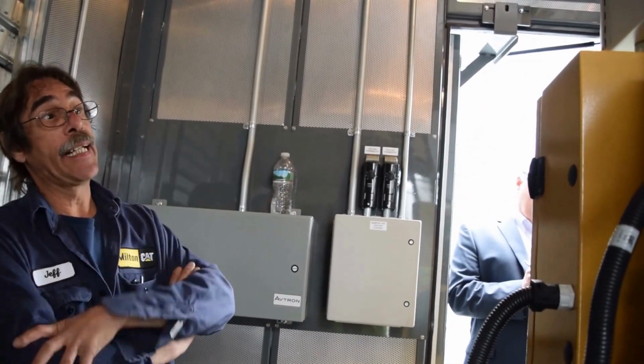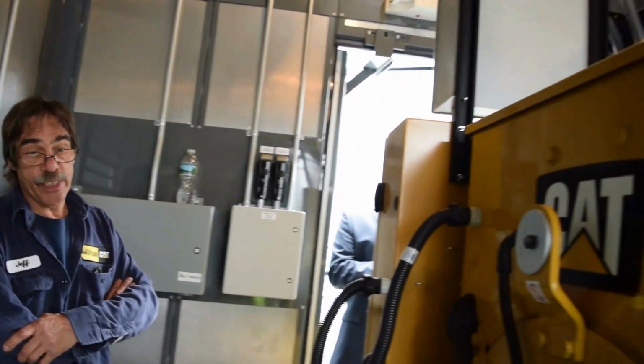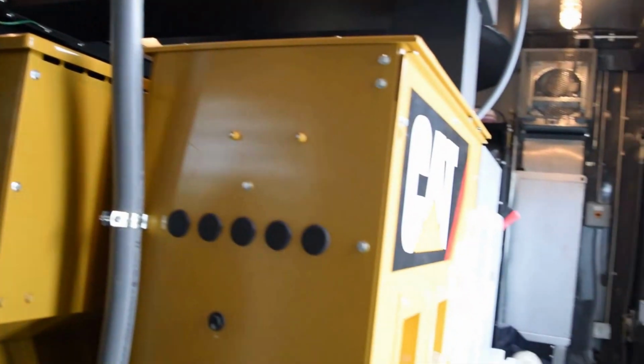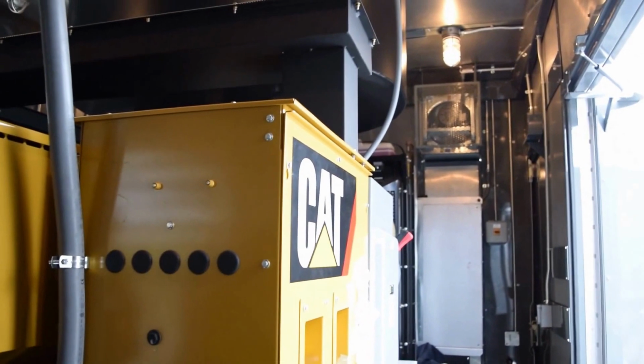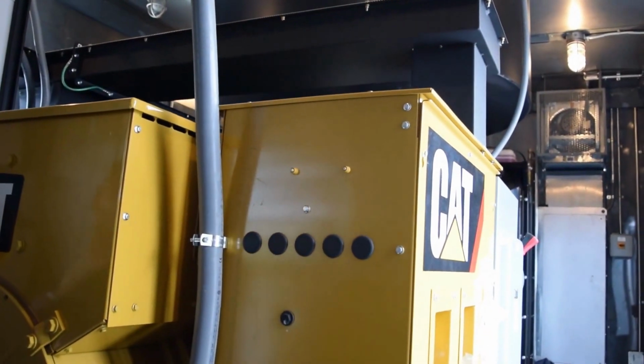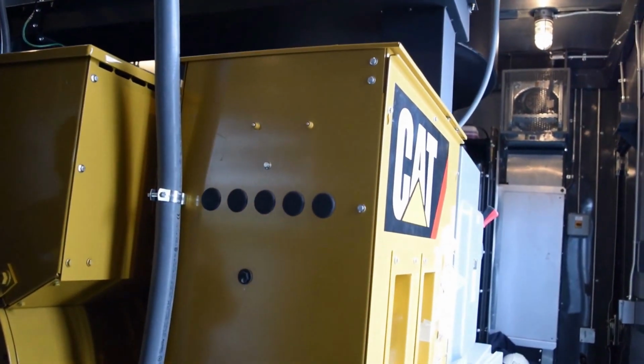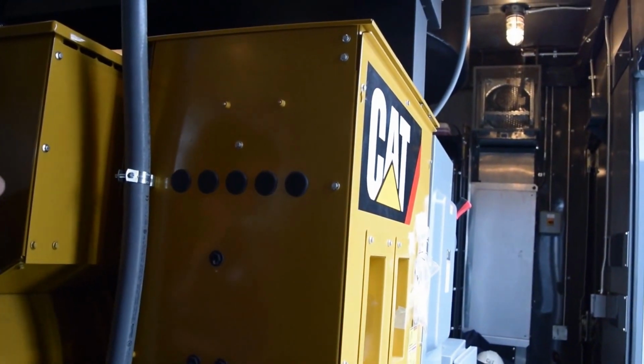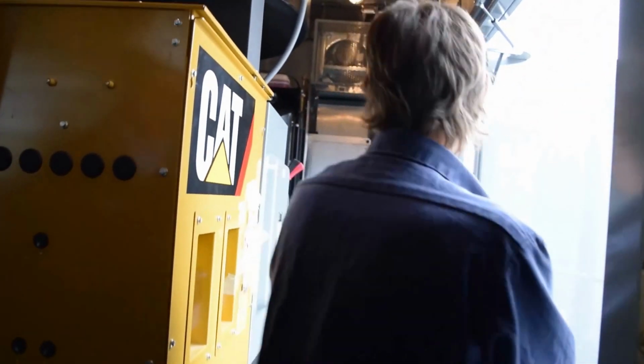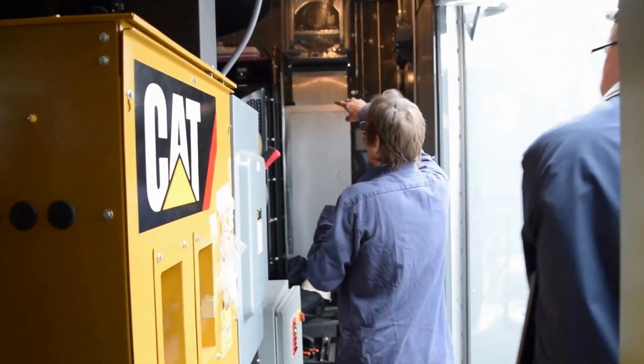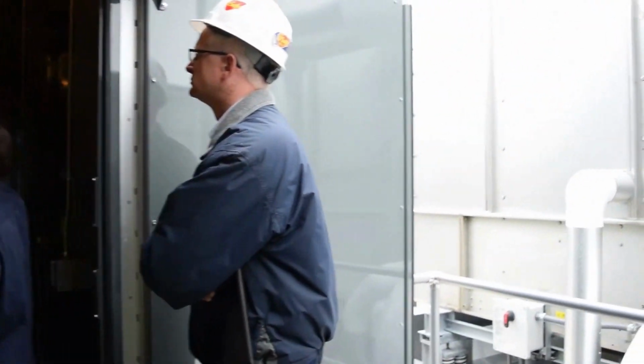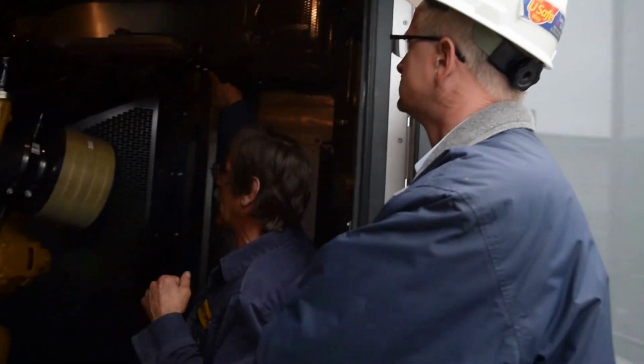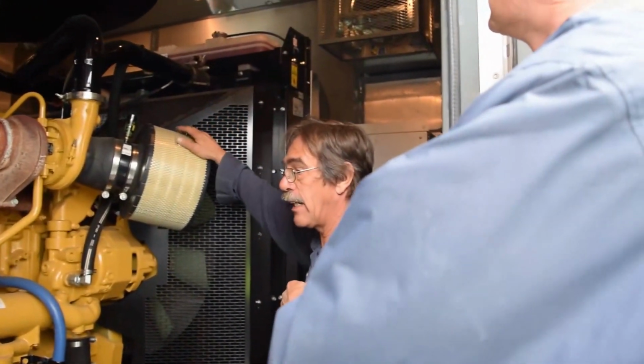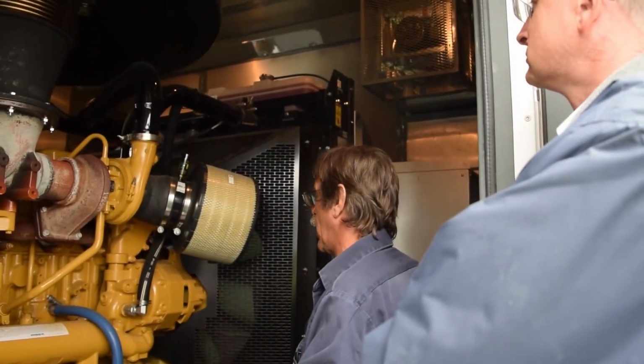On the opposing side of the engine, we have our air filters, which have service indicators on them. You'll see they're green, and it'll go red if you get dirty air cleaners. That's kind of few and far between. Most gens in this type of application stay very clean. You have your see-through tank, so it's like a huge sight glass for your coolant and your radiator cap up the top, and just like your car, you'd never want to open that when it's hot.